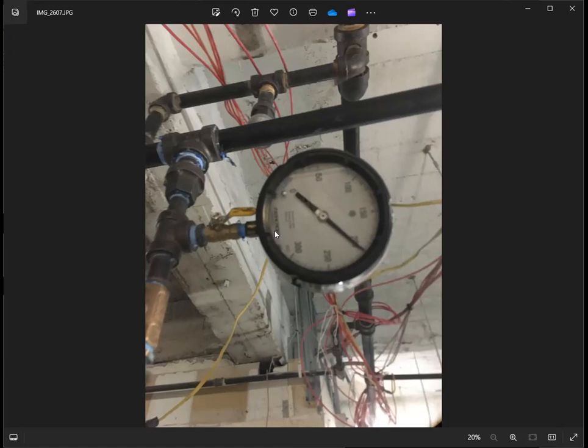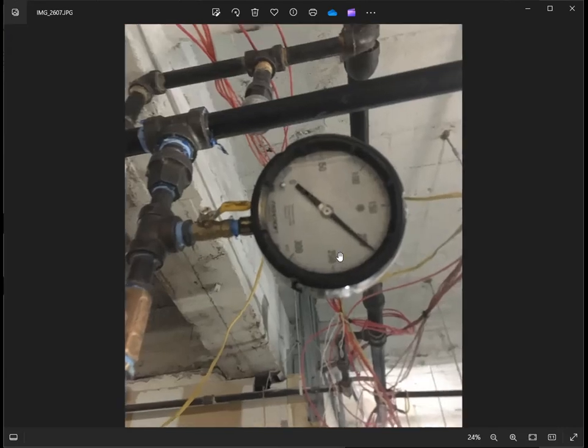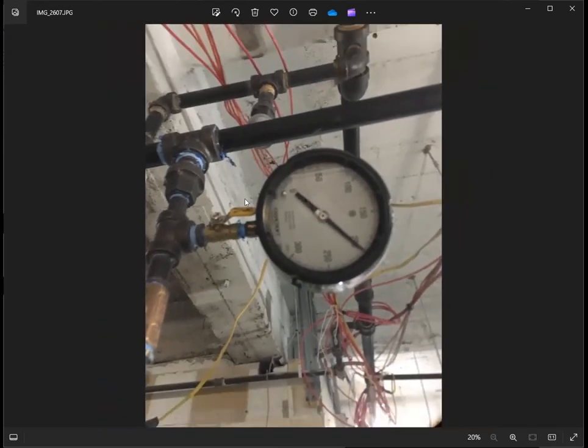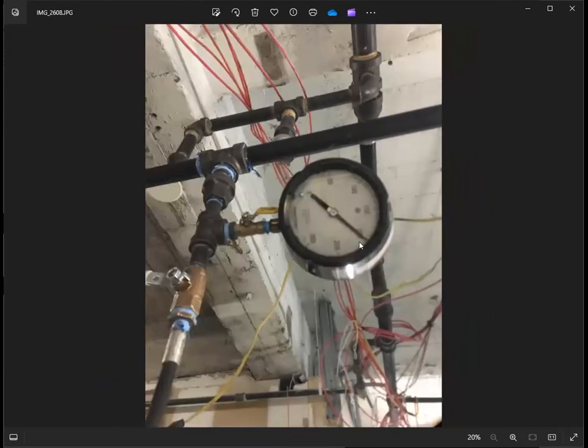So upon arrival on the job, we're doing a hydro test. The requirement is a 2-hour test without any pressure leak, pressure drop, or any visible leak on the pipe. The thing that I'm showing here is the assembly of the pressure gauge when I took it upon arrival. It's much better to take a photo of it because it's a 2-hour wait for the test, so that during those 2 hours you could do the visual inspection of the installation of piping materials, the supports, and all other documents that you need to evaluate as per drawing specs, as per drawing plan.